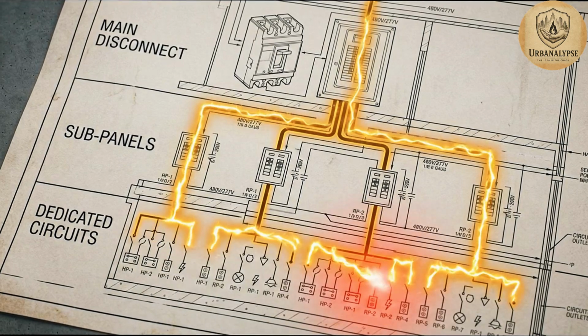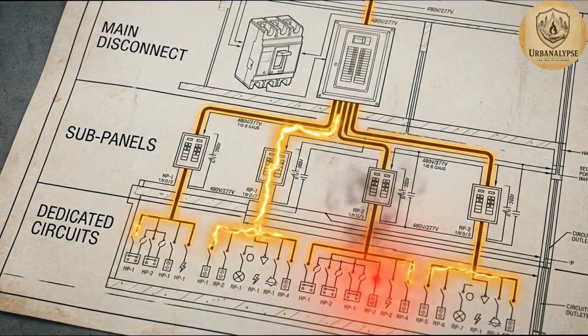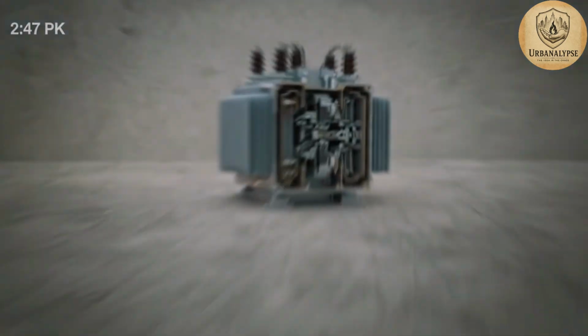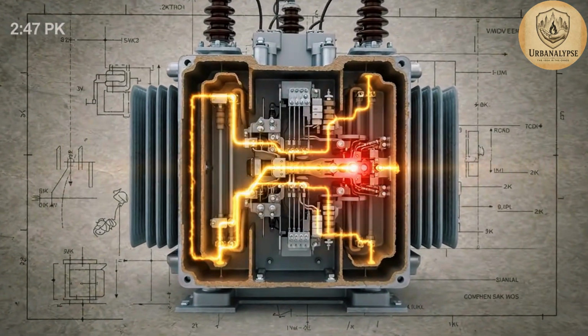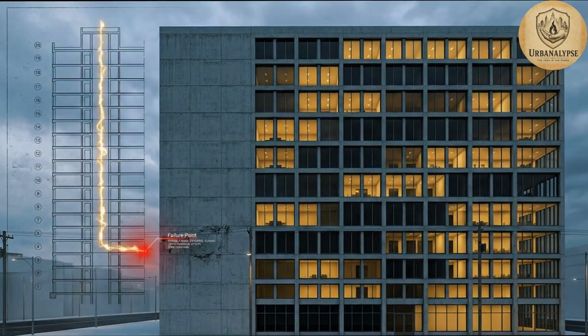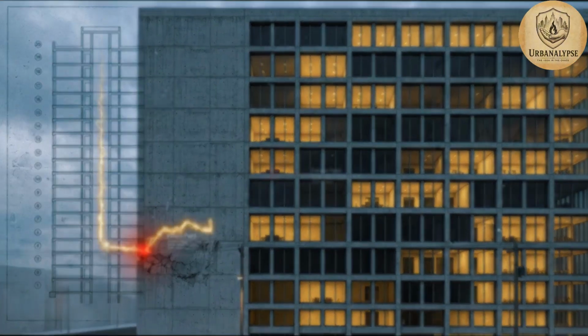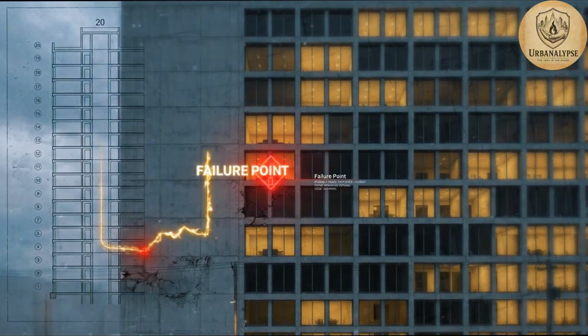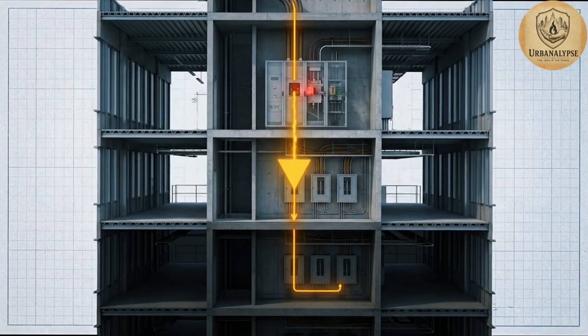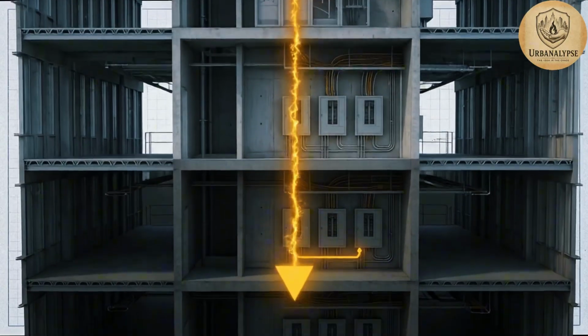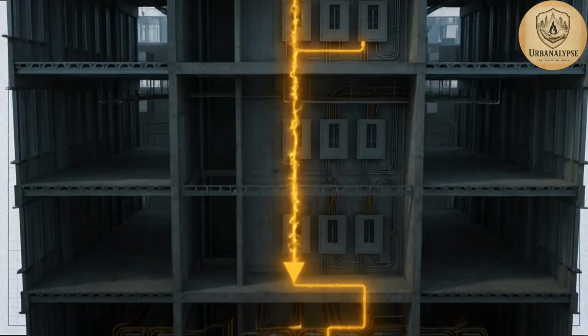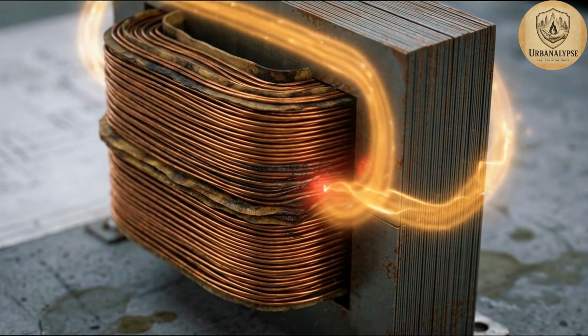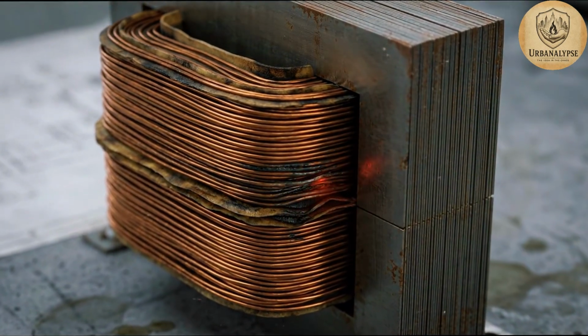Every high-rise runs on a fixed electrical hierarchy. Main disconnect, sub-panels, dedicated circuits, each stage built to protect the next one downstream from fault current. When the grid drops, that hierarchy, not the outage itself, decides who keeps light, who keeps water, and who gets nothing until a utility crew finishes repairs outside on the street.